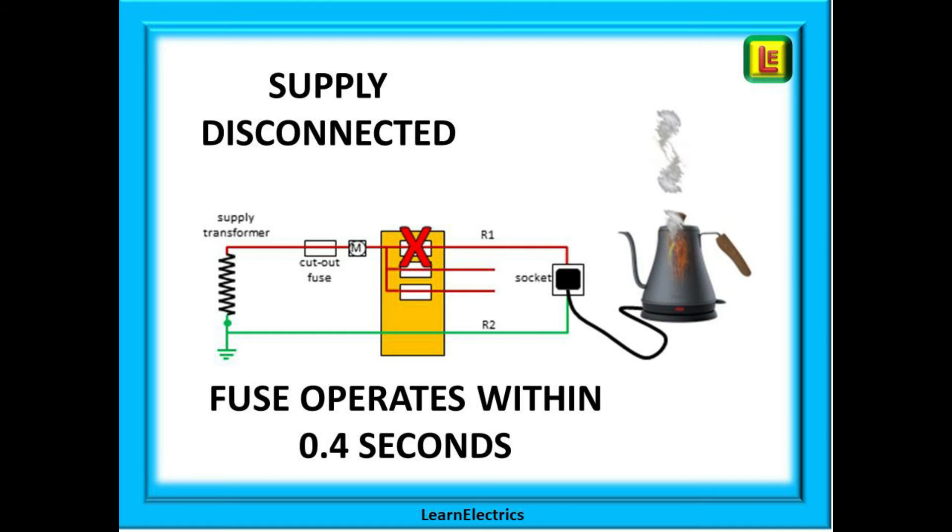If this 700 amps fault current stopped at the earth point of the transformer, nothing would happen to the fuse and you would continue to receive an electric shock. The 700 amps must return through the fuse to cause the fuse to blow or the MCB to operate. If the fault current does not complete the full loop from the fault to the supply transformer and back again to the kettle, then the fuse is never going to disconnect the supply. Think about it for a few seconds. If the 700 amps doesn't go through the fuse, then how is the fuse going to blow?